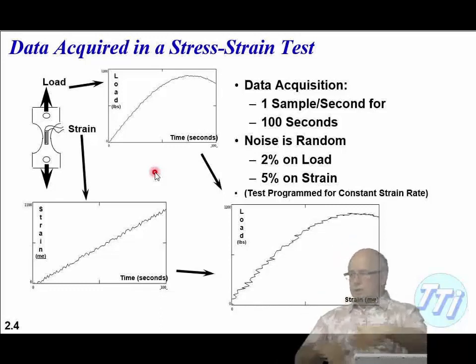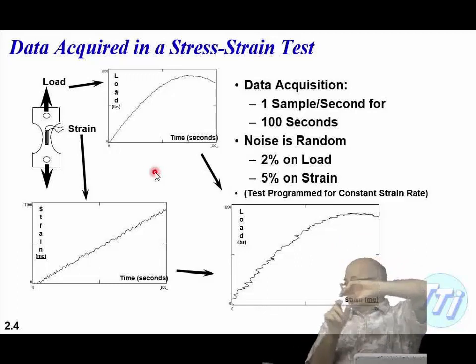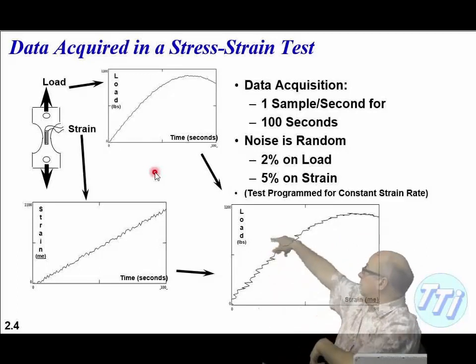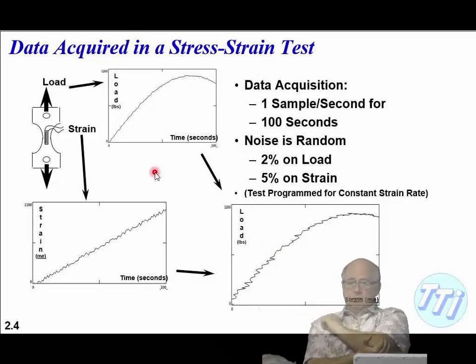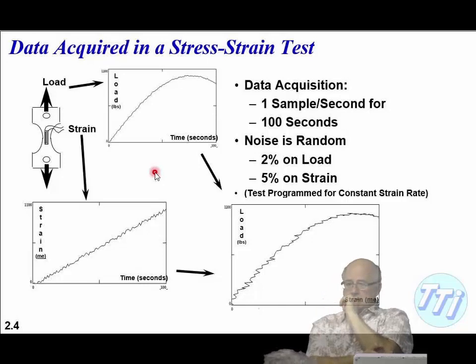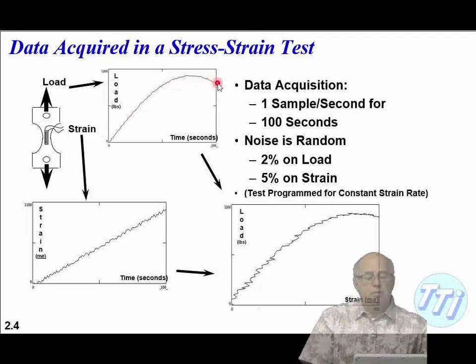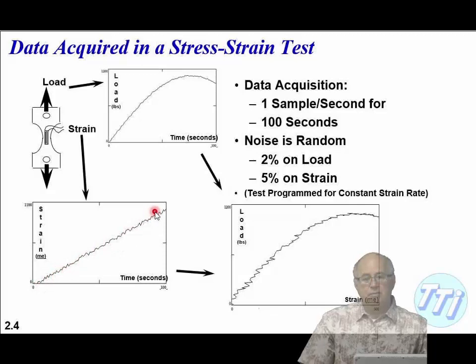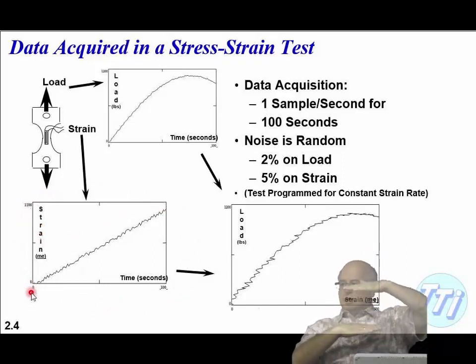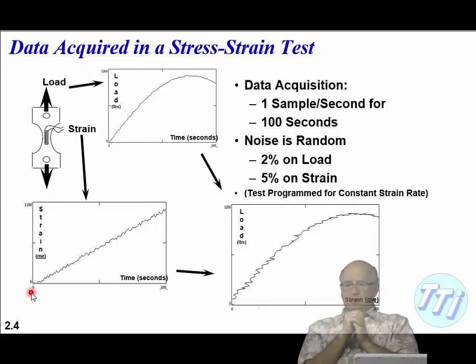When you're doing a stress-strain test, you take a crosshead machine. In this particular test, it was displacement control because as time went on, the load went up and then dropped off as we get into necking. Whereas if you were doing load control, the load would just keep going up. The strain just keeps going up as a function of time, so this must have been under displacement control — basically raising the crosshead at a constant rate and measuring the resulting load. Displacement control is the most common approach.